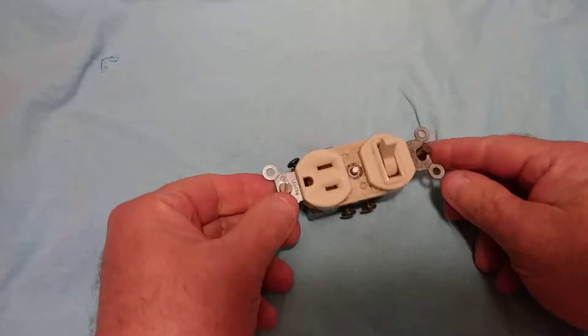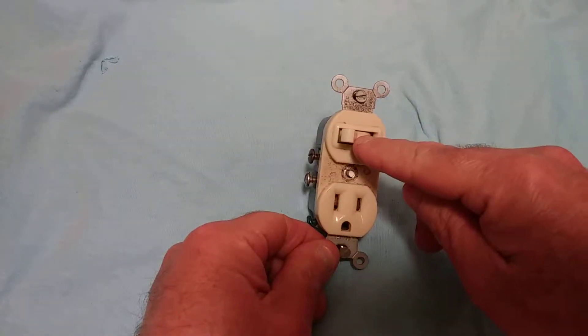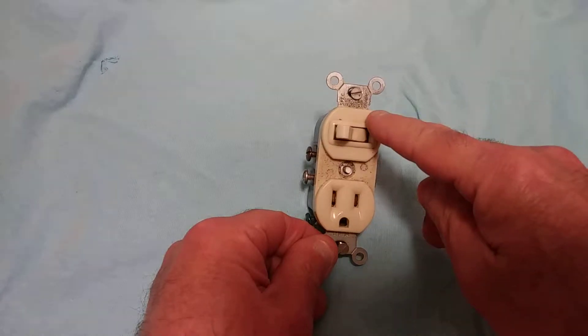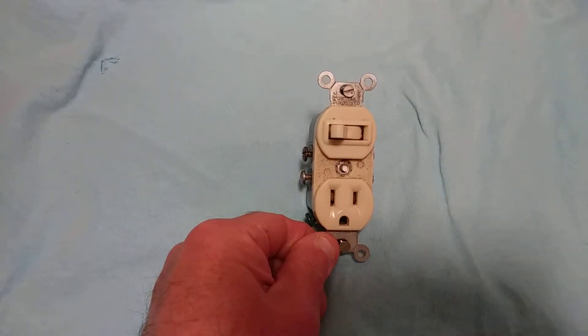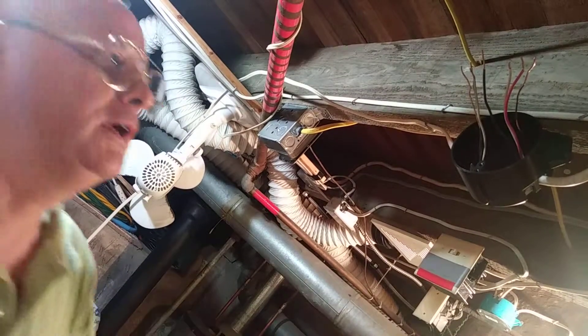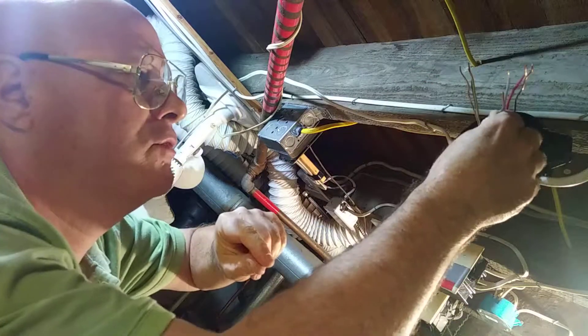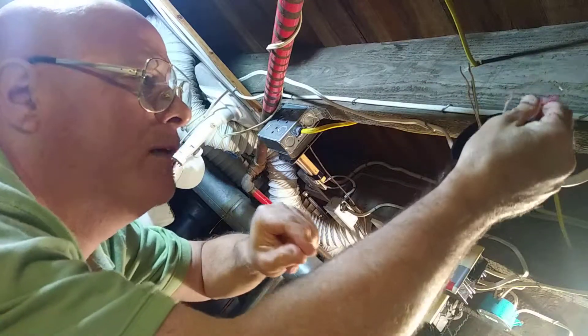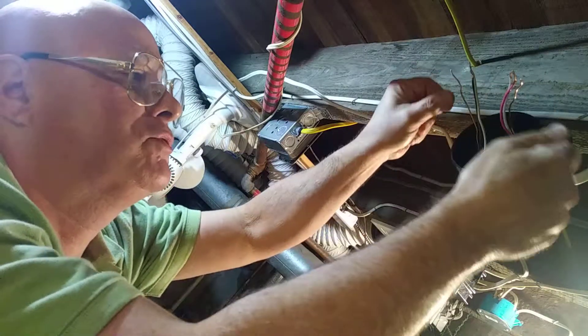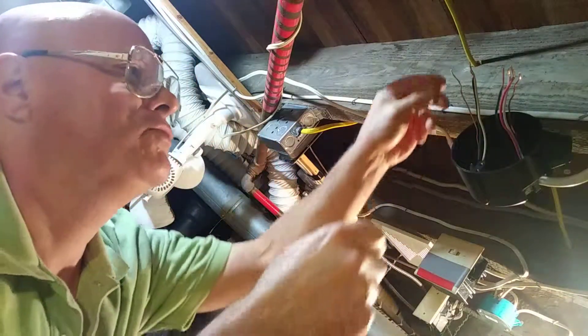I'm going to show you how to wire this. We're going to have this switch operate a light and this outlet on all the time, and this switch here turn on and off a light. So this is the power coming in — black, white, and ground — going out to the switch/outlet combo unit. We're going to hook this up so that the light is controlled by the switch.